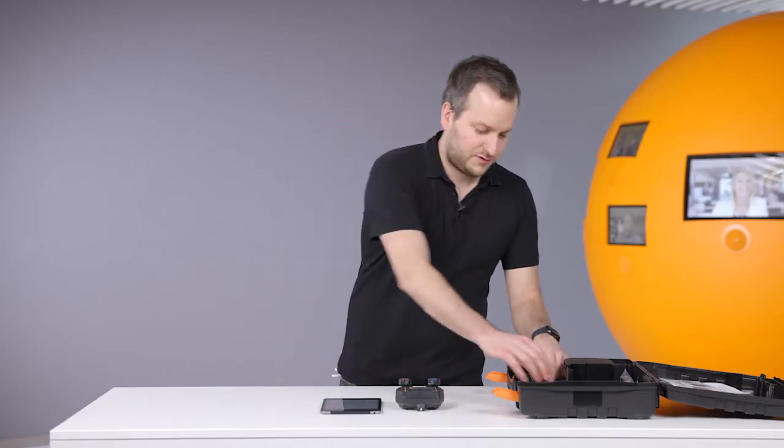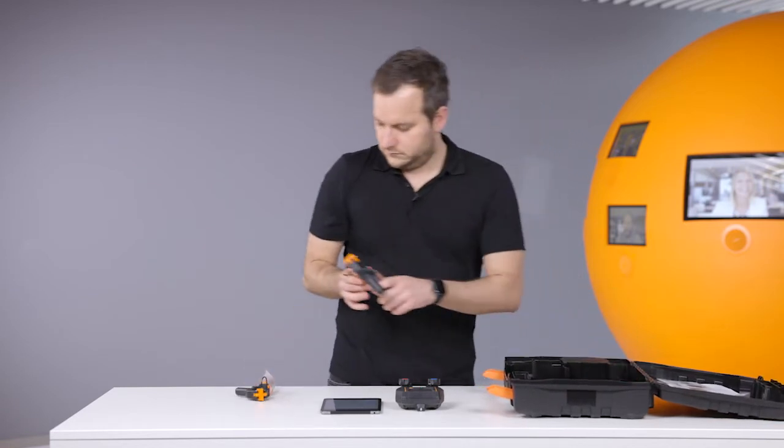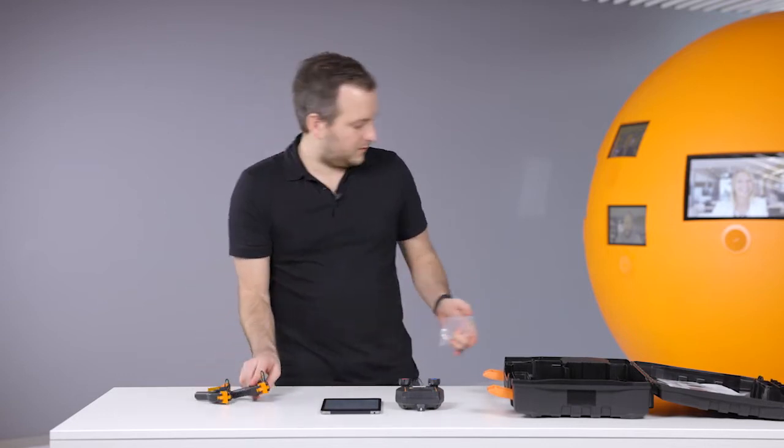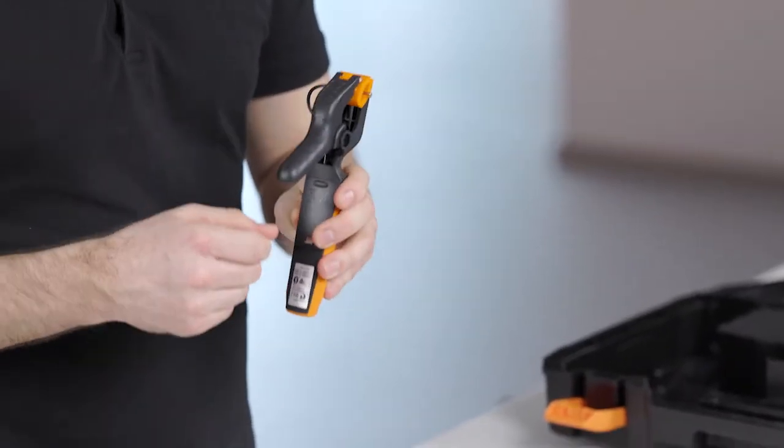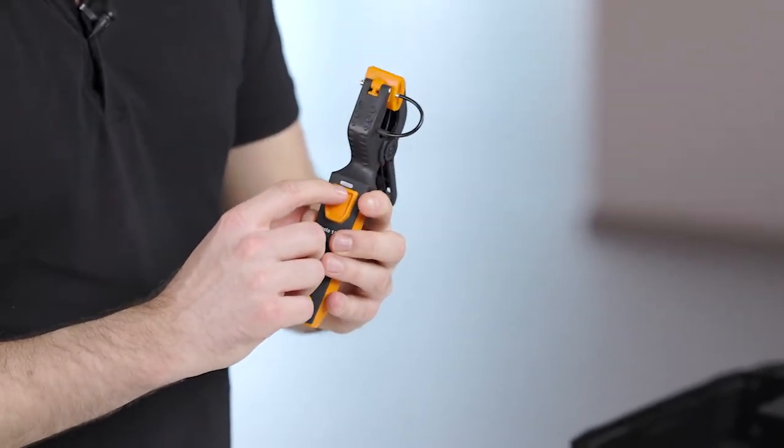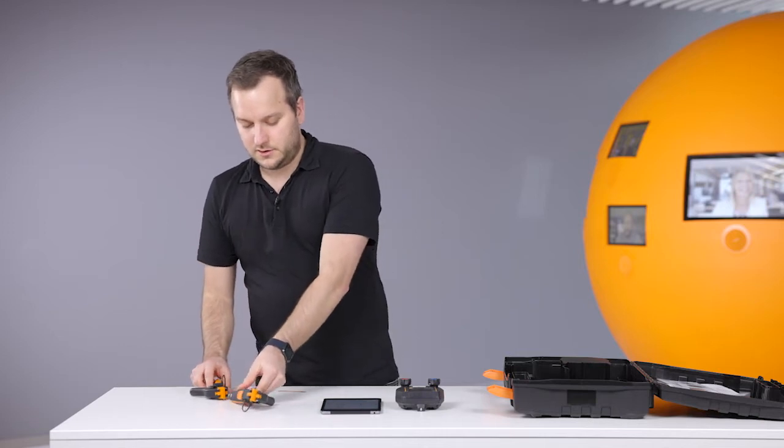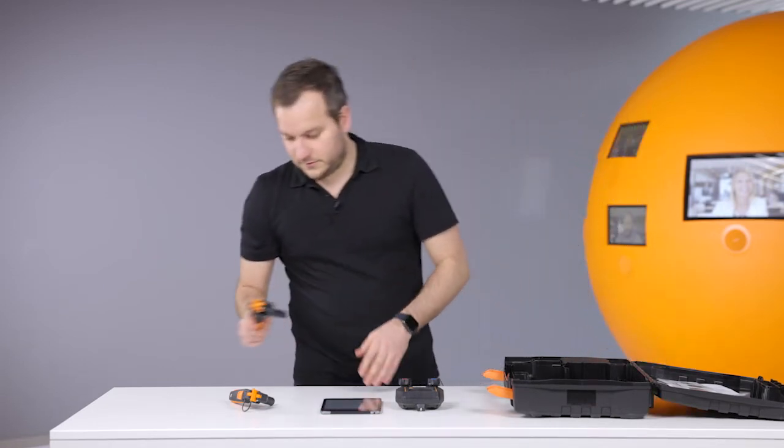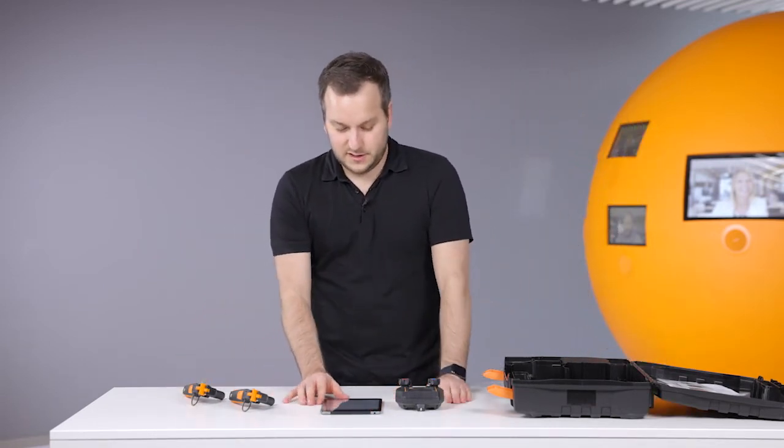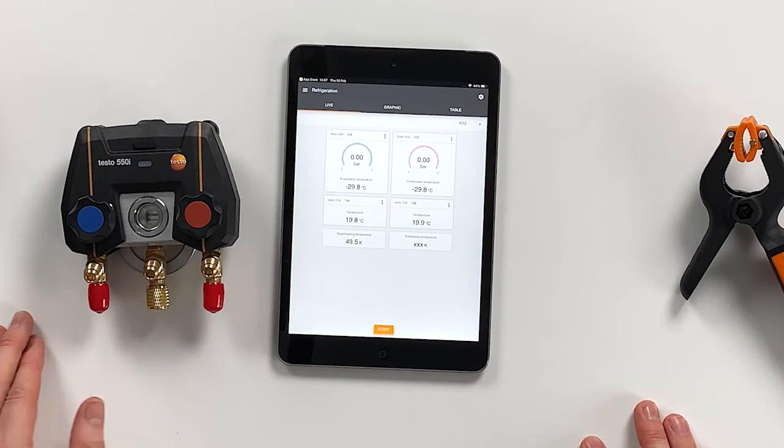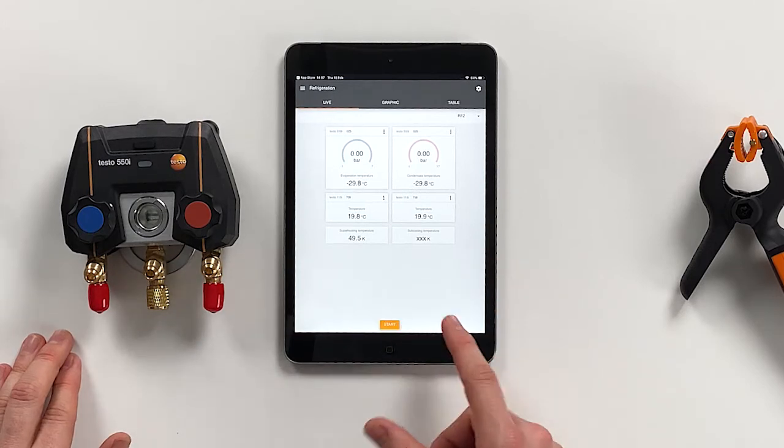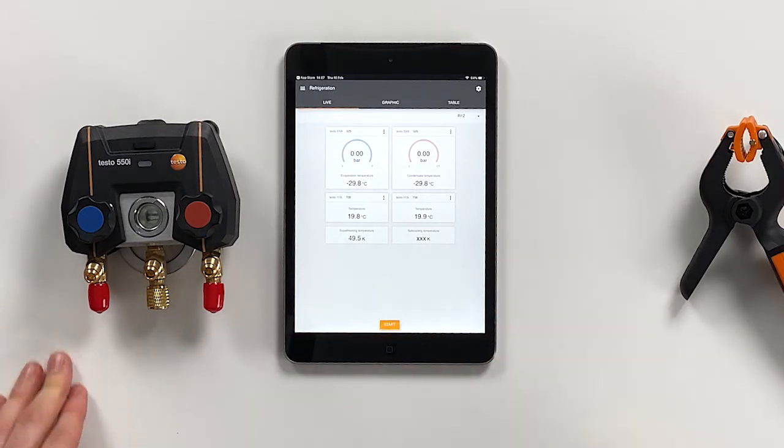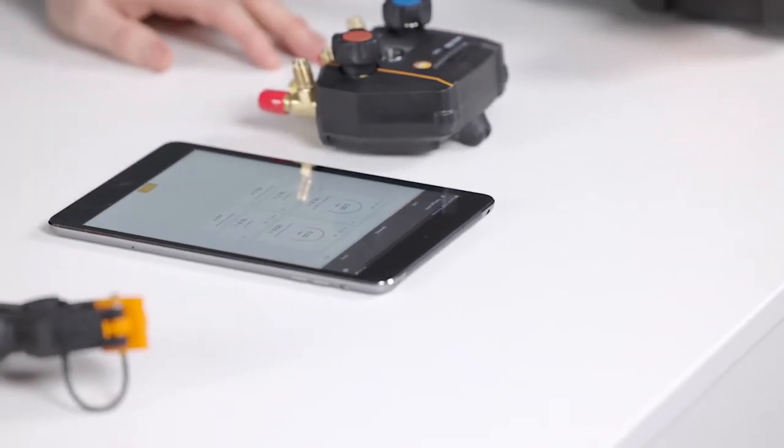To actually do a good measurement, we have to have the wireless temperature probes. Let's take them out. To power them on, you just have to remove this strap, just pull it out. Then you can see that the probes go into a searching mode. Now both probes are searching for a connection. As you can see, the first probe is already connected, and the second probe is connected. When both are connected, the app also starts to calculate the superheating temperature and the subcooling temperature.